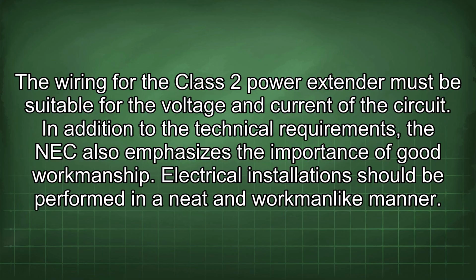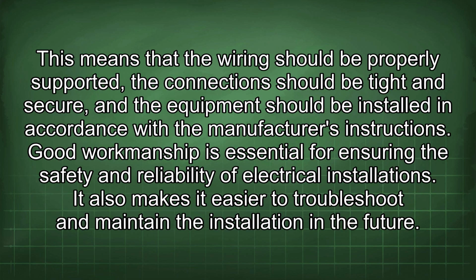In addition to the technical requirements, the NEC also emphasizes the importance of good workmanship. Electrical installation should be performed in a neat and workmanlike manner. This means that the wiring should be properly supported, the connections should be tight and secure, and the equipment should be installed in accordance with the manufacturer's instructions. Good workmanship is essential for ensuring the safety and reliability of electrical installations. It also makes it easier to troubleshoot and maintain the installation in the future.